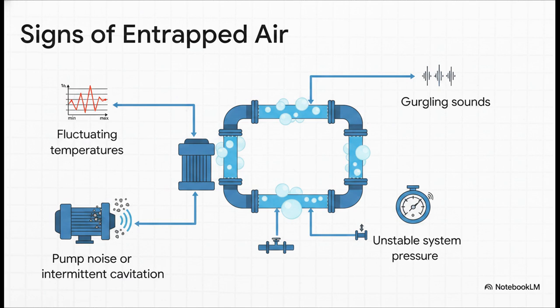Air. It's one of the most underrated causes of cooling issues. It gets trapped in high points, creating pockets that block flow and kill heat transfer. The signs can be subtle. You might see temperatures that are jumping all over the place. You might hear strange gurgling noises from the pipework, or the pump might sound like it's full of gravel. If you've done any maintenance that involved draining the system, air needs to be at the top of your suspect list.